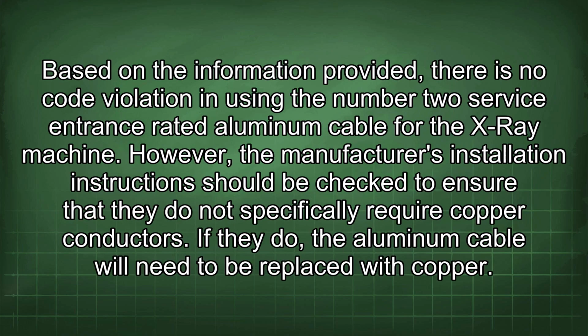Based on the information provided, there is no code violation in using the number 2 service entrance rated aluminum cable for the X-ray machine. However, the manufacturer's installation instructions should be checked to ensure that they do not specifically require copper conductors. If they do, the aluminum cable will need to be replaced with copper.